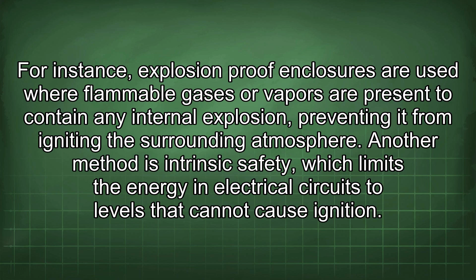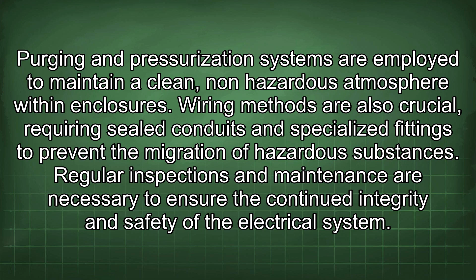Another method is intrinsic safety, which limits the energy in electrical circuits to levels that cannot cause ignition. Purging and pressurization systems are employed to maintain a clean, non-hazardous atmosphere within enclosures. Wiring methods are also crucial, requiring sealed conduits and specialized fittings to prevent the migration of hazardous substances. Regular inspections and maintenance are necessary to ensure the continued integrity and safety of the electrical system. Compliance with Article 500 is essential in preventing fires and explosions in hazardous locations, protecting personnel and property. Understanding the specific requirements for each classification and ensuring proper installation and maintenance are key to a safe electrical installation.